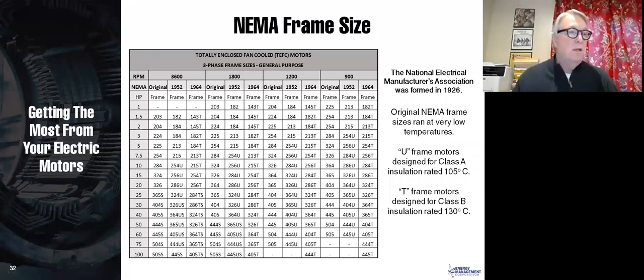So first of all, let's talk about frame size. NEMA standardized frames, and that's so terrific because it used to be you had a motor built by GE or by Westinghouse or by Siemens, and you had to replace it with another motor that was made by that same manufacturer. And they said, for the good of the user, we're going to standardize motors. And so in the original standardization, here were the frame sizes. For instance, a 1 horsepower, 3,600 RPM motor was a frame 203.